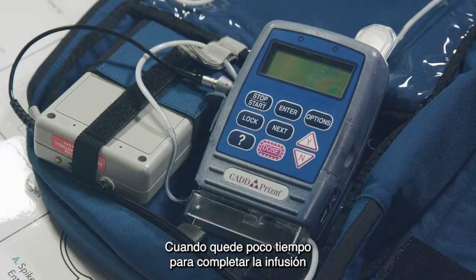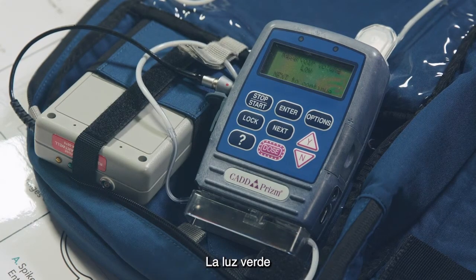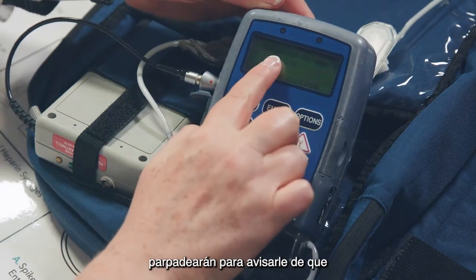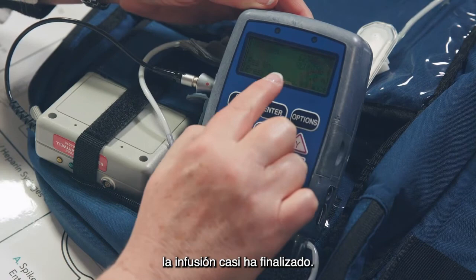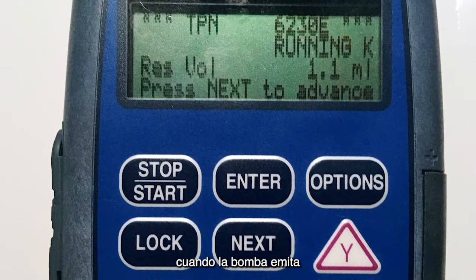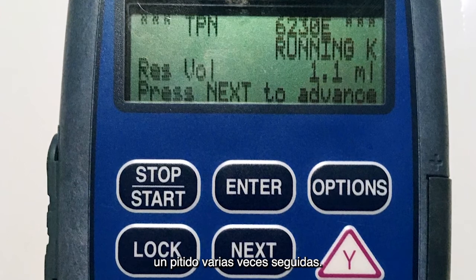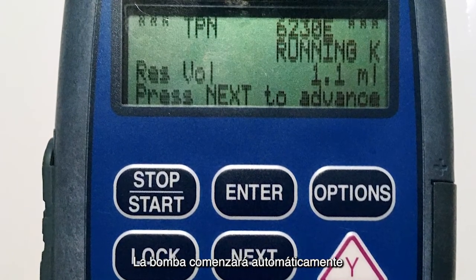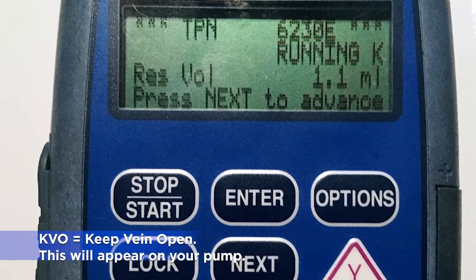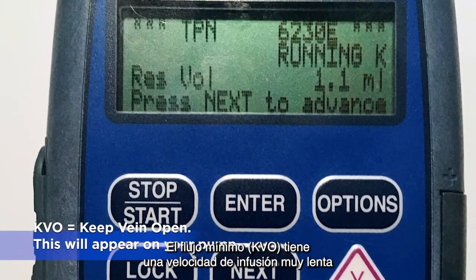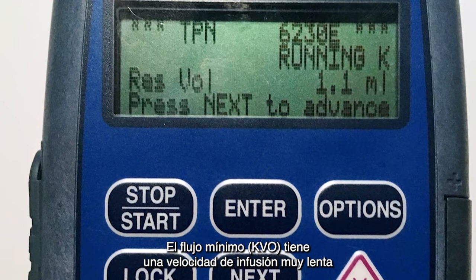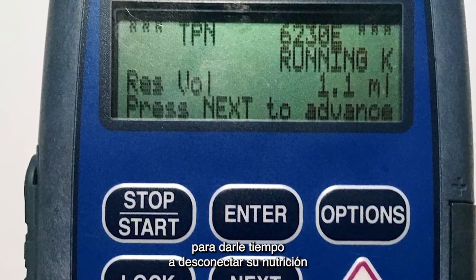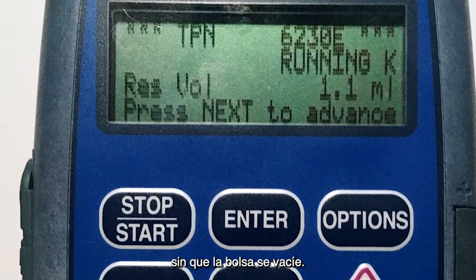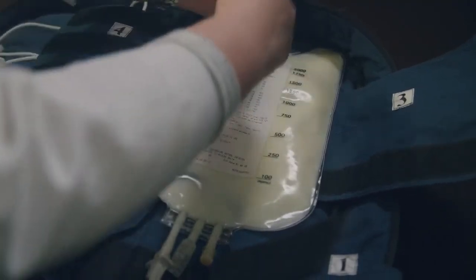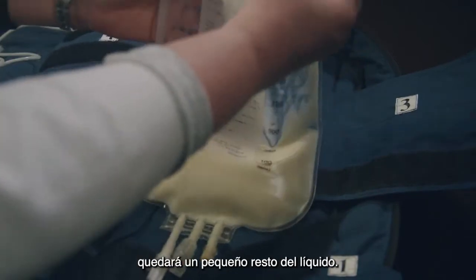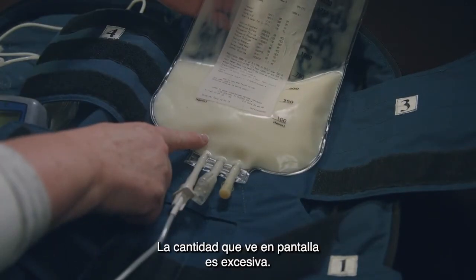When your infusion is almost complete, your pump will beep once, and both the green and the amber light will flash to alert you that the infusion is nearly done. You will know it is time to stop your TPN infusion when the pump beeps several times in a row. The pump will automatically begin infusing at the KVO rate until the stop button is pressed. KVO rate is a very slow rate of infusion to give you time to disconnect your TPN without the bag becoming empty. There will be a small amount of fluid left in your TPN bag. This is overfill.